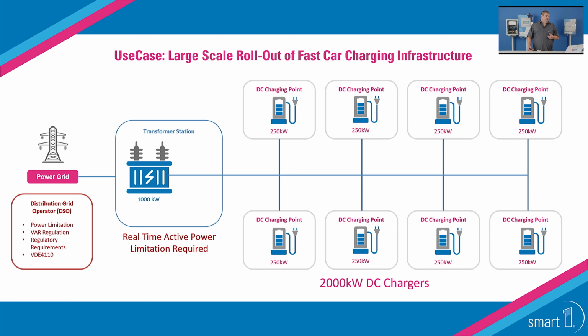In addition, we have the requirement from the distribution grid operator, DSO. The DSO requires, by VDE 4110 or 4105, to regulate the power of the charging station through a grid operator interface, so you need to limit the power of the charging stations if the grid operator requests you to. We also have requirements to do reactive power regulation based on regulatory requirements, and all of this also needs to be fulfilled with the EMS.